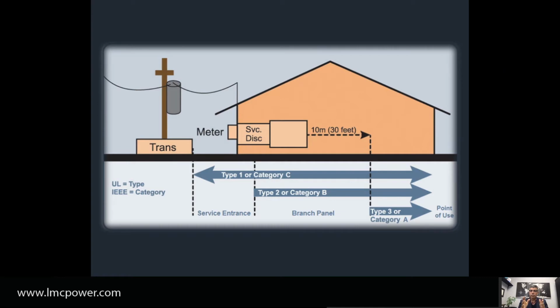Any distribution panel, go around that range and you should be good. And category C, or type 1, could be at the entrance of the building. Now, if you see type 1, it goes the long range. You can put a surge protector that's 150 kA all the way and connect it right to where the load is. It'll work perfectly. There's no reason why not. The problem is that a category C may cost you $2,000 and a category A would cost you $300, so you might not need to put a $2,000 piece of protection where you can use a category A and be able to reduce the price. Also, the size of the unit will be a lot smaller if you go closer to the load.